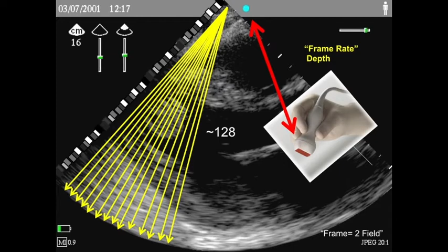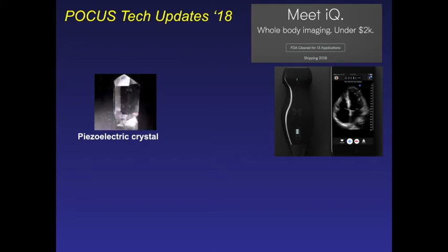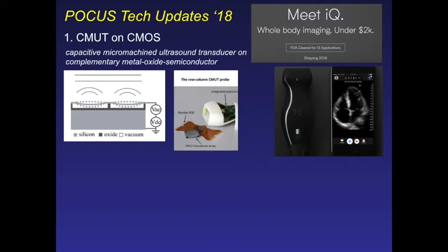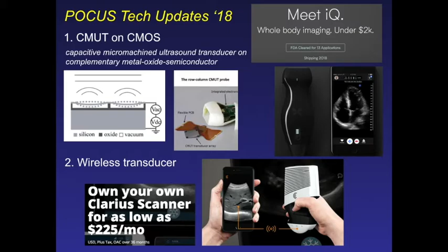Just a quick update from 2018 that is important to the point-of-care ultrasound field: this concept of the piezoelectric crystal has been challenged by the company that has made the Butterfly, as they call it. This is the transducer attached to an iPhone. It works through what's called CMUT on CMOS, which is chip technology to create an ultrasound transducer, which reduced the price. The other update is that the wire that connects the transducer probe to the phone itself, through a different company, has been eliminated, and you essentially Bluetooth your image across to your screen.